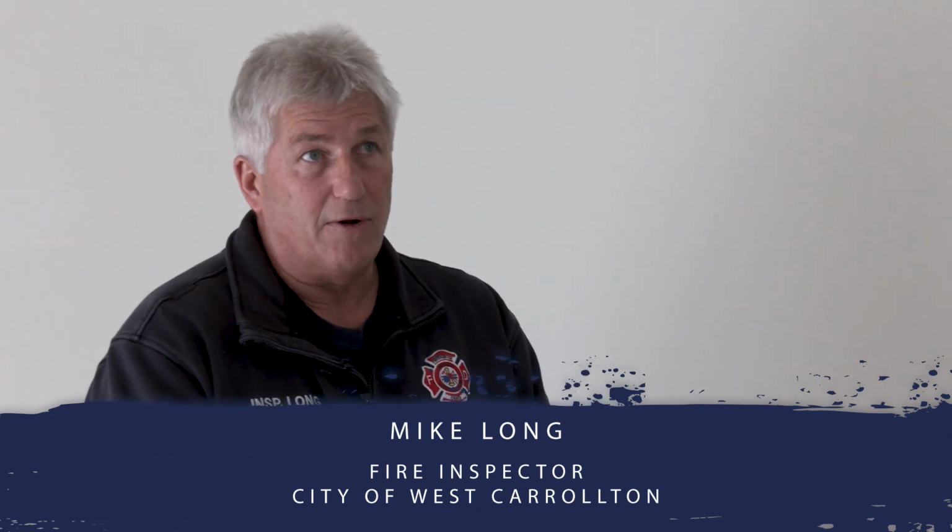So Mike, we just came through the 2 bedrooms and came out the hallway. My question is, are these smoke detectors electric, are they battery, or are they a combination of either one or the other one? The particular smoke detectors in this unit are all battery operated. The code did not require them to be electronically connected. That didn't start until 1996. These were built prior to that, so these are standalone battery operated detectors.